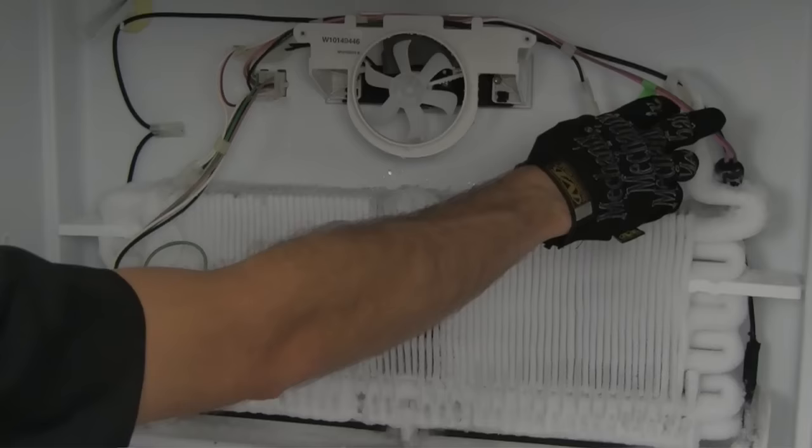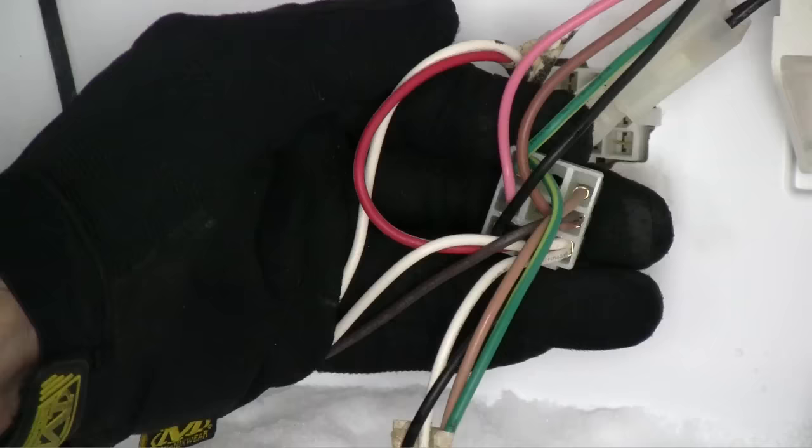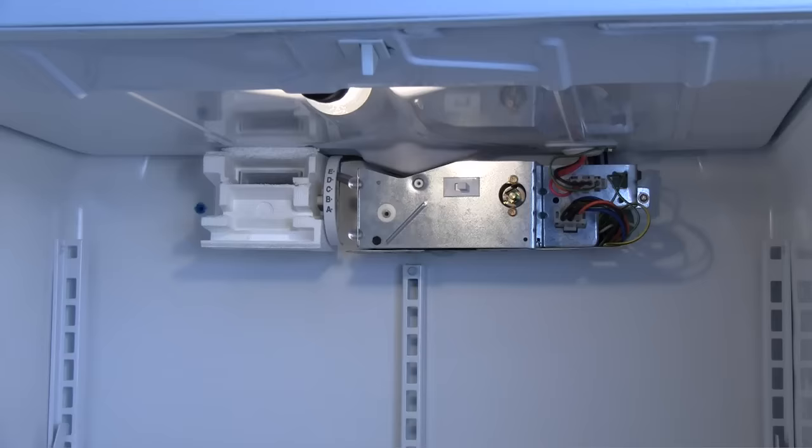The most common mechanical failure is the bimetal thermostat failing to close and allowing power to flow through to energize the heater. The thermostat can be checked for continuity when it is cold. If everything is frozen and the thermostat has infinite resistance it needs to be replaced.